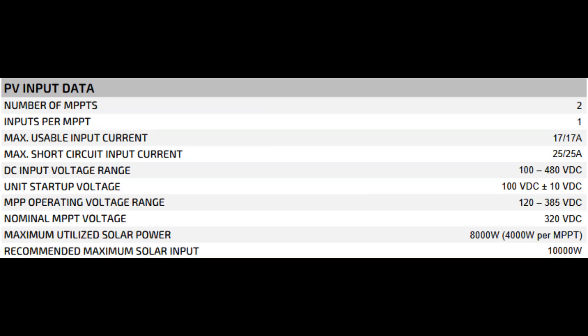Now for the PV input data, the solar side. Number of MPPTs 2, inputs per MPPT 1, max usable input current 17 amps, max short circuit input current 25 amps, DC input voltage range 100 to 480 volts DC, unit startup voltage 100 volts DC plus or minus 10 volts DC, MPP operating voltage range 120 to 385 volts DC, nominal MPPT voltage 320 volts DC, maximum utilized solar power 8,000 watts, 4,000 watts per MPPT, recommended maximum solar input 10,000 watts.